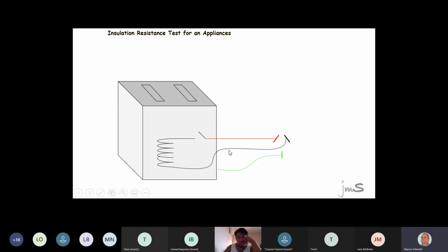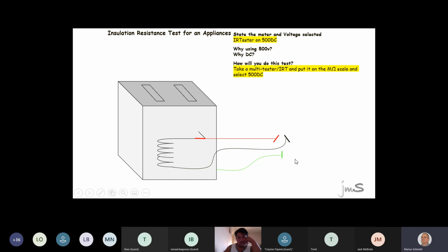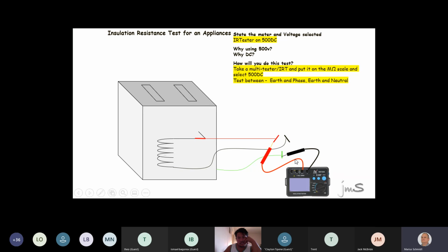Happy? Now, there's one very important thing you have to do with all appliances. Look what's going to happen with that switch, because otherwise you do not test the switching wire. You switch it on. A lot of the appliances, you can't. You have to keep your hand on the on position. But now we go. We're going to take a tester and we're going to put it across earth and phase. And that's the same test. A 500 volt insulation resistance tester. We test between earth and phase, earth and neutral.